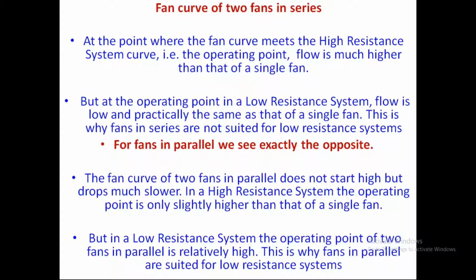We can see the exact opposite, where on the fan curve, automatically the high resistance is not there. So the low resistance of the system improves the operating point of the existing two fans, and ultimately parallel fans are suited to all the industries where the airflow changes have to be achieved, or the air changes have to be achieved. In many of the textile mills, they go for 2 fans or 3 fans or 4 fans to achieve this.